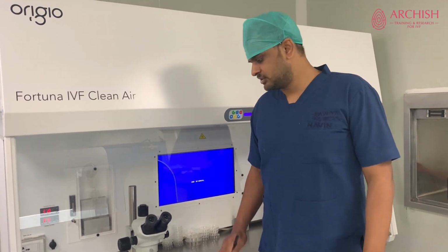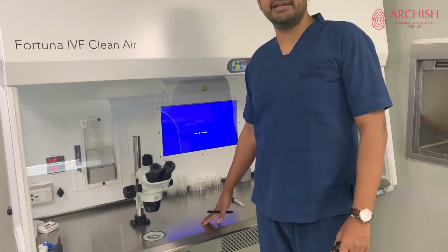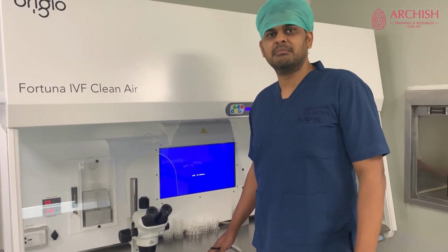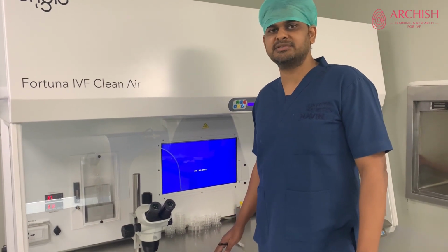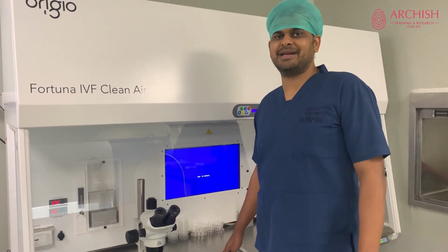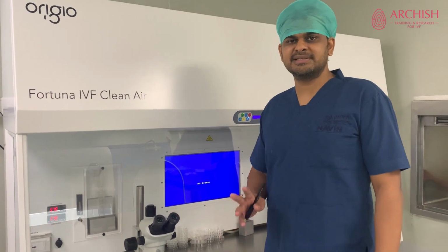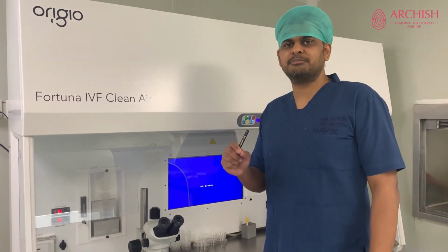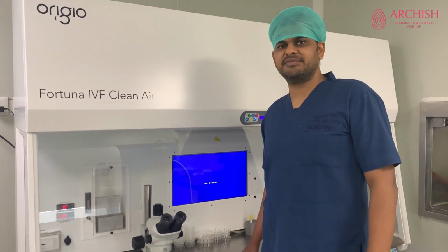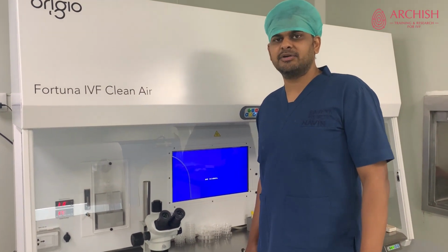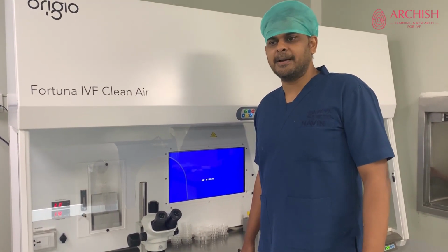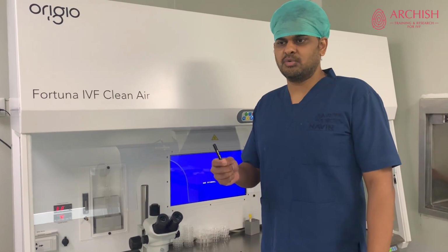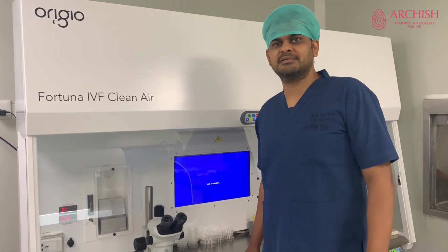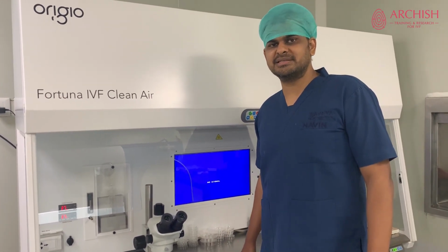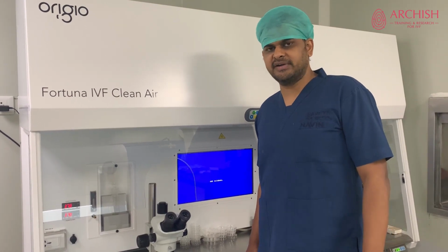So for the reading, the heated surface is at 37 degrees. It's not important to check it every day, but once every 3 days it's a good practice to keep the temperature probe on this and check it. The reason I say once in 3 days is because keeping the probe or sticking it to the particular surface can be a little tricky, and you might not always be the best quality control checker for the laminar airflow.